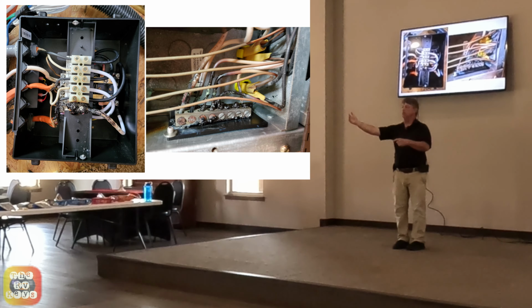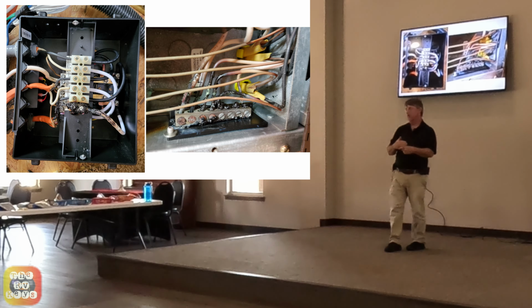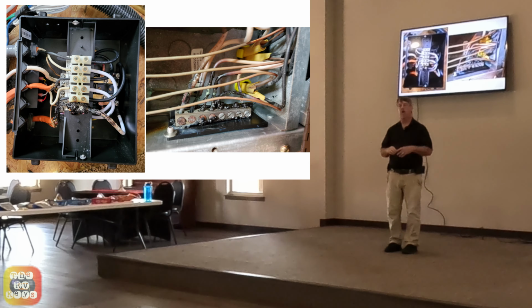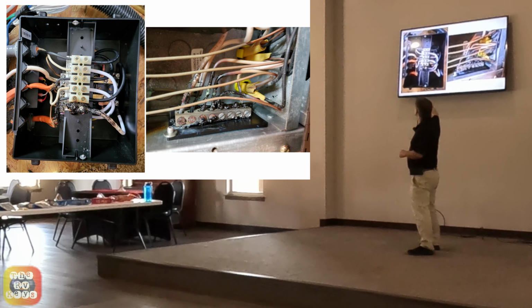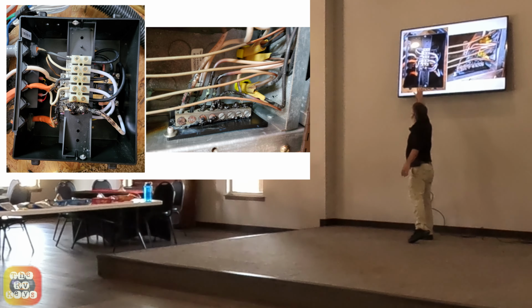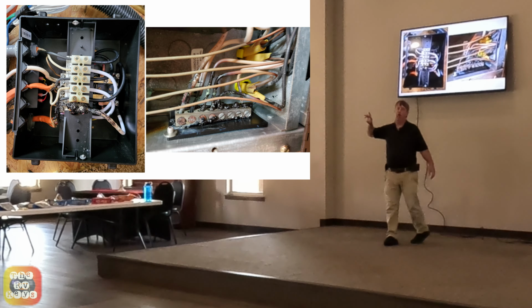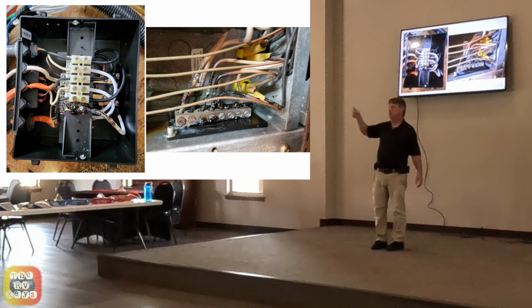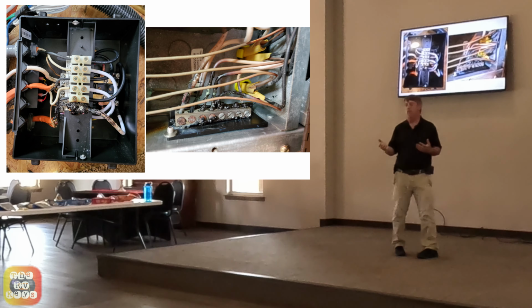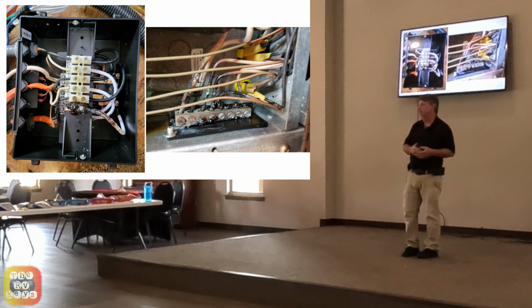So now you've got double the expansion, double the contraction. So it's very useful, and it's something I always do when I'm around a power panel that I'm working on. I will check the tightness of those lugs. When I checked these 2 wires, the other 2 wires turned about 1/3 to 1/2 turn.